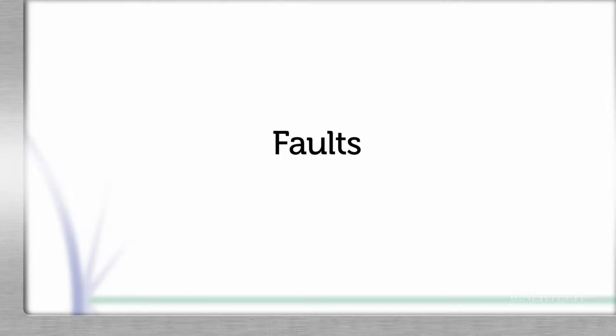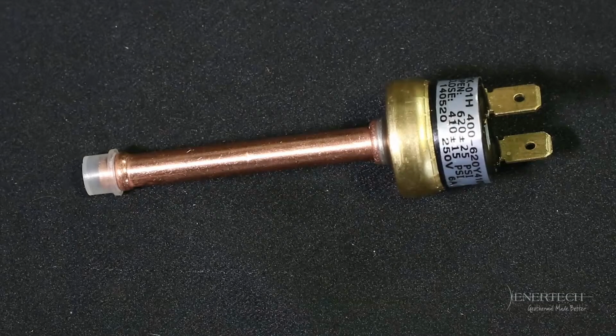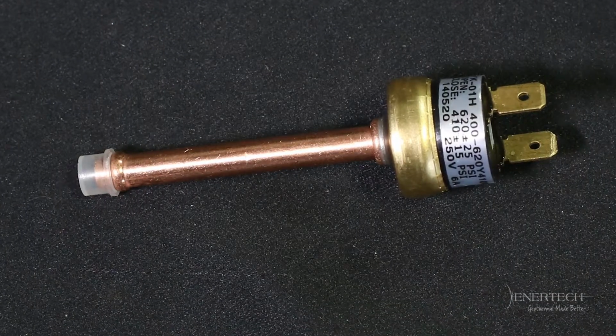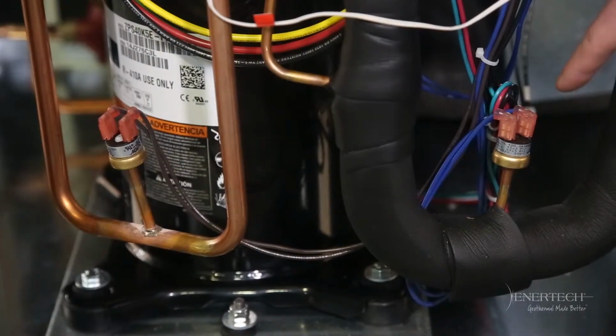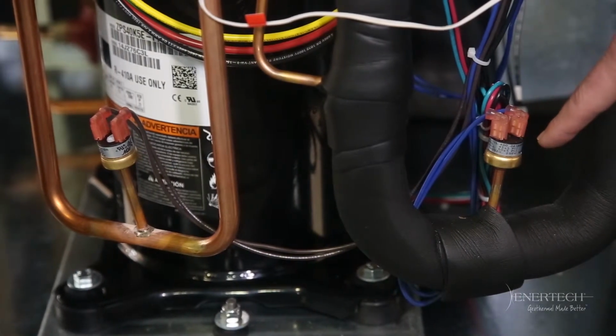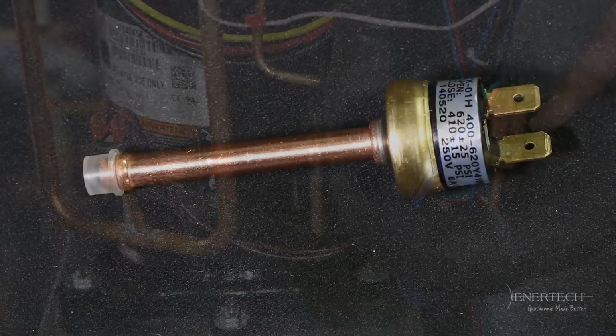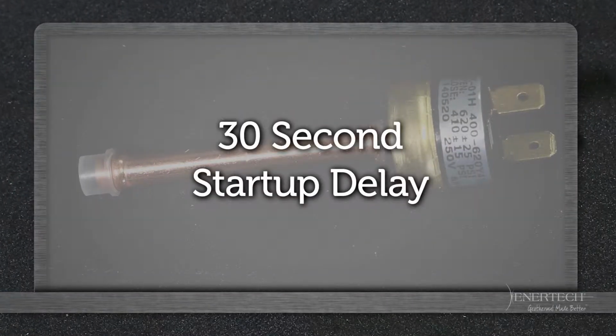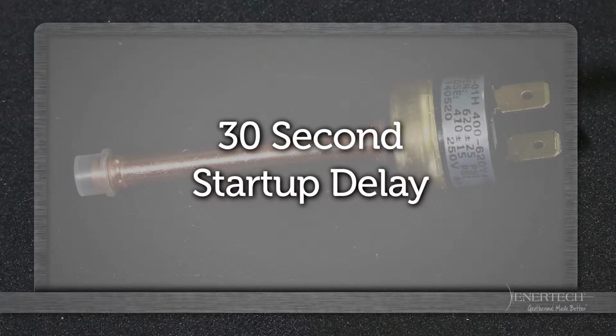Here's a little more detail on the faults. If the low pressure switch is open continuously for 30 seconds, the compressor operation will be interrupted and the control will go into fault retry mode. At startup, the low pressure switch is not monitored for 30 seconds to avoid nuisance faults.